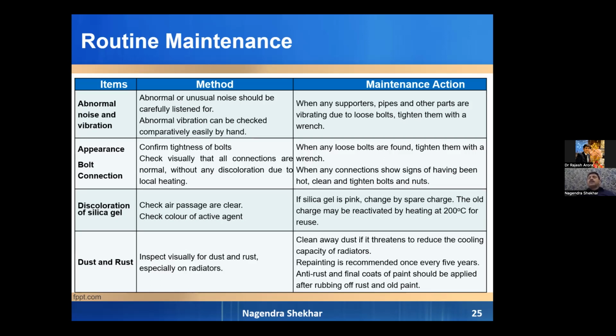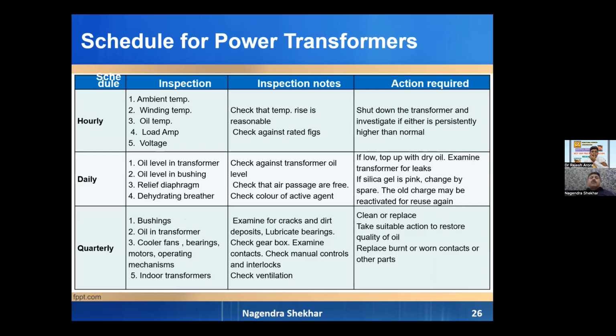Appearance of bolted connections: wherever our connectors are connected with the transformer bushing, we have to see whether they are properly connected or not, and whether there are any marks of heat and so on. Discoloration of silica gel: if it is pink, we have to change it or reactivate it. Dust and rust: we have to ensure repainting of our transformers also. For power transformers, as I told you, we have to ensure on an hourly basis ambient temperature, winding temperature, oil temperature, load on the transformer, and output voltage. Similarly, daily we have to check the oil level in bushings where bushings are oil filled, and the relief diaphragm and dehydrating breather.